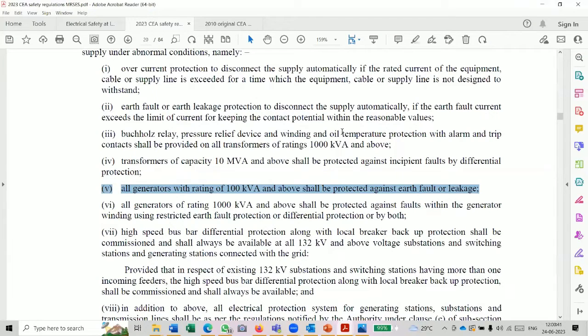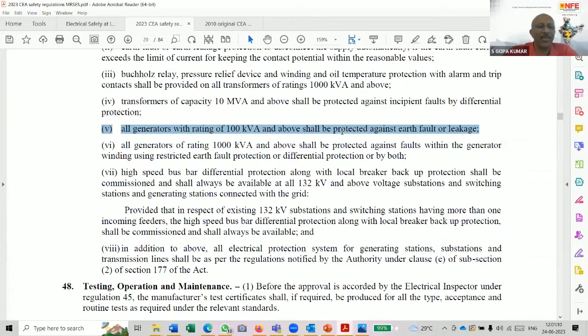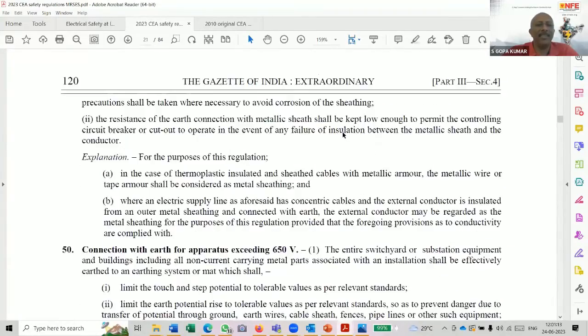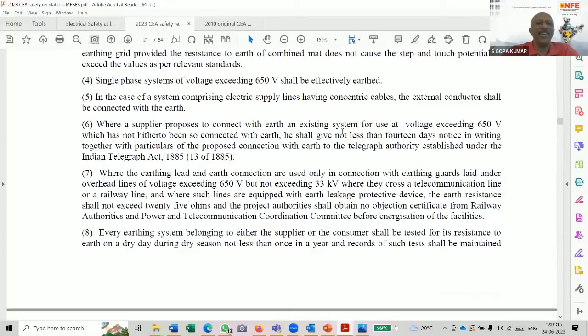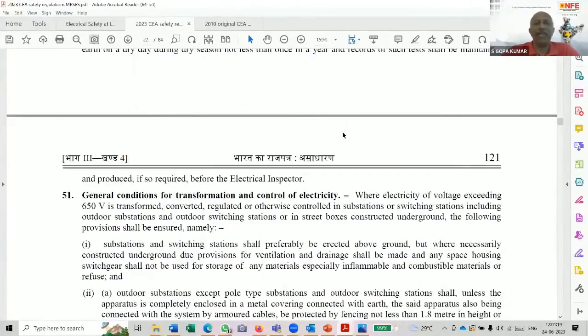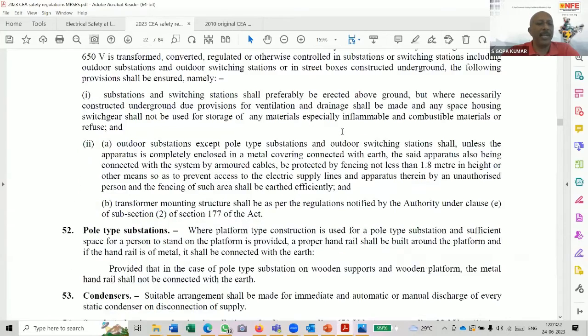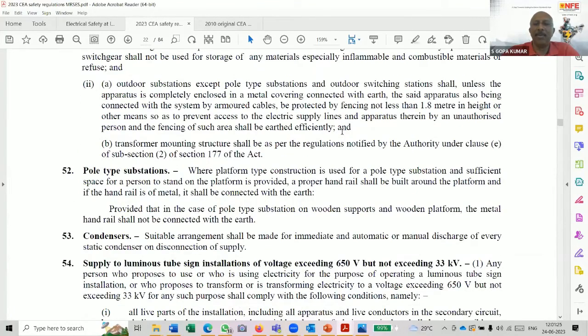Sir, actually this 650 volt was existing almost 100 years back. At that time there were no standard distribution voltages at various levels. That is repeated and existing for the past 100 years, I can say. Now we are in 2023. From 1937, we can reach 2037 also. It's quite unfortunate that we still follow 1937, the voltage 650 volt. But in the draft it was much better, 1000 volt, but again 650 came into the picture. And we have to wait another 10 years to get a chance to change.